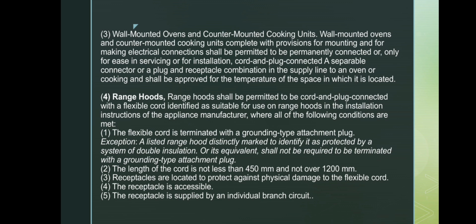where it's installed. For range hoods, a cord and plug connection is allowed if certain rules are followed. The cord must have a grounding type plug unless the hood is marked as double insulated. The cord length must be between 450 millimeter and 1200 millimeter. The receptacle must be placed where the cord won't be damaged, must be accessible, and must be supplied by its own individual branch circuit.